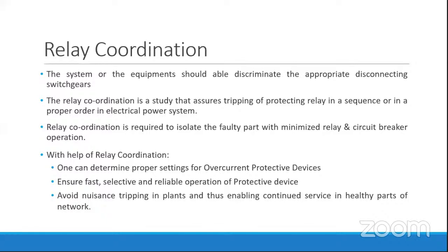As I said, relay coordination is done to isolate the faulty part and to minimize the faulty condition. Relay coordination should be done in such a way that it isolates the fault with the minimum operating time of the relay and circuit breaker. With the help of relay coordination, we can determine the protection settings of the protective equipment for overcurrent conditions, and also for overvoltage and undervoltage conditions.